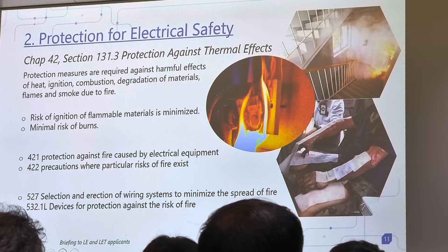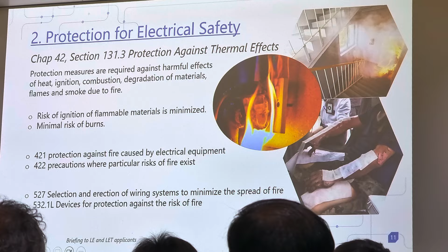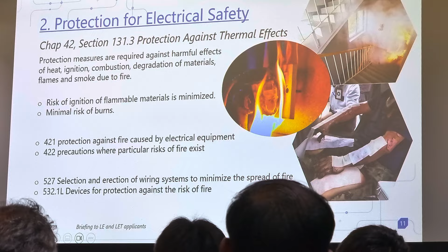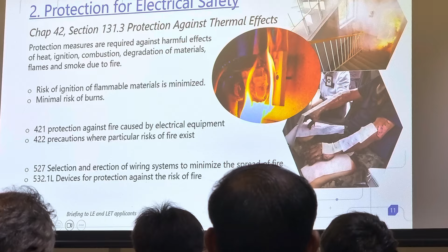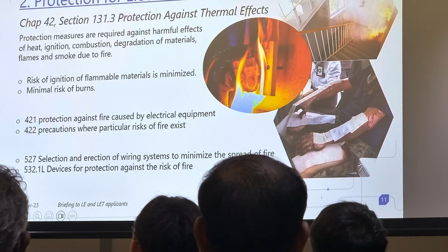So the source of the heat can also be external. So how do we make sure that if there are heat sources from external, we will not propagate the effect of electrical distributions? So we could talk about in 421, protection against fire caused by electrical equipment. 422 talks about when there are particular risks. For example, if you have escape routes, places where people evacuate during fire, and that's the place where the fire occurred, it's not correct. So where there are escape routes, exit staircases, etc., that's where we should protect against occurrence of fire.